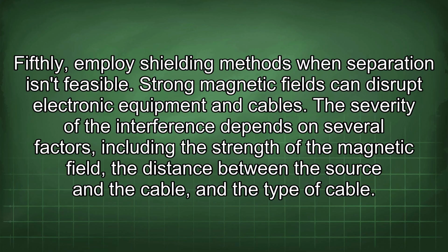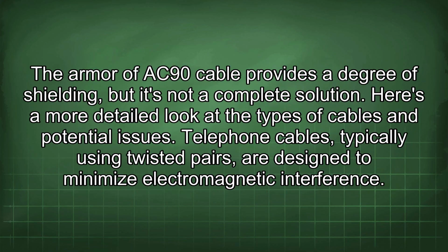Strong magnetic fields can disrupt electronic equipment and cables. The severity of the interference depends on several factors, including the strength of the magnetic field, the distance between the source and the cable, and the type of cable. The armor of AC90 cable provides a degree of shielding, but it's not a complete solution. Here's a more detailed look at the types of cables and potential issues.